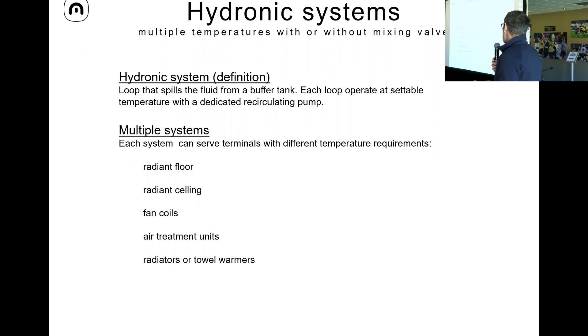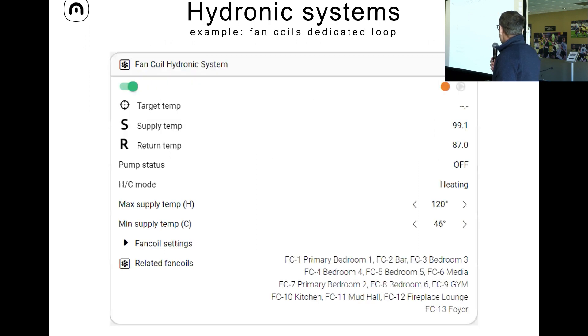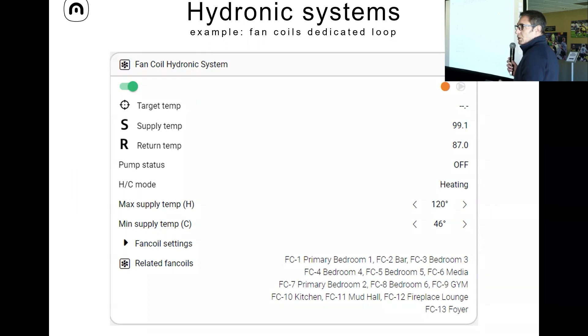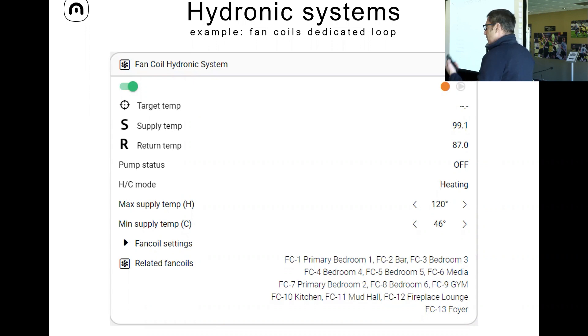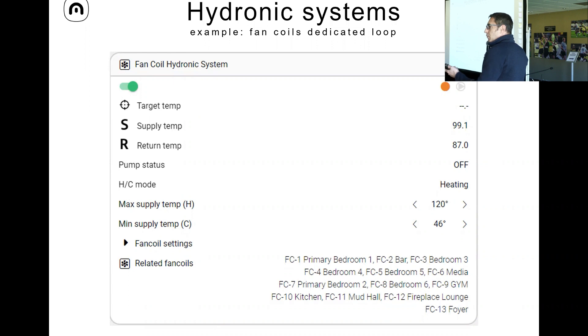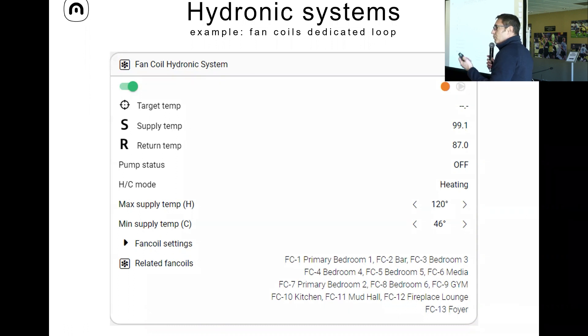Here is an example of a hydronic system — in this case a fan coil loop. You can see in orange or blue what the heating and cooling mode of that loop is, and you can see the supply and return temperature. One common component of any hydronic loop is the pump — you need one recirculator per loop. You can set the maximum or minimum temperature on the loop, so if you have wood on a radiant floor and don't want it above 40 degrees, you set the maximum to 40 and that loop will never exceed it.